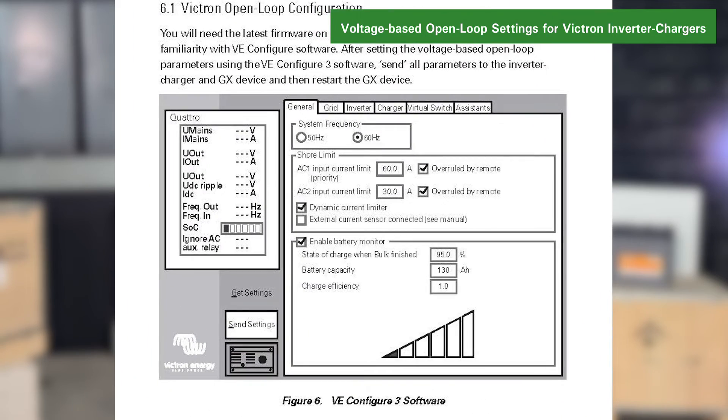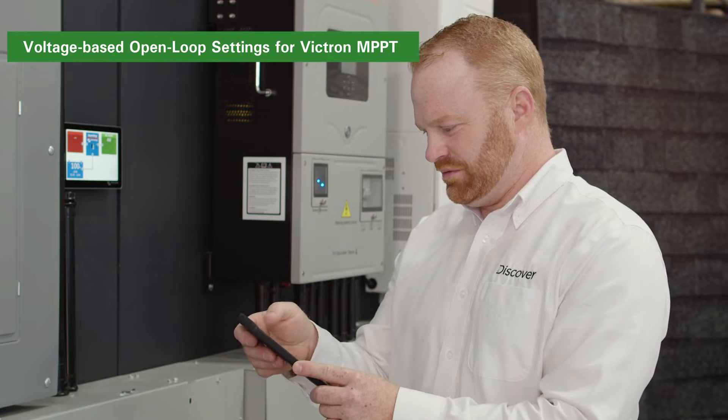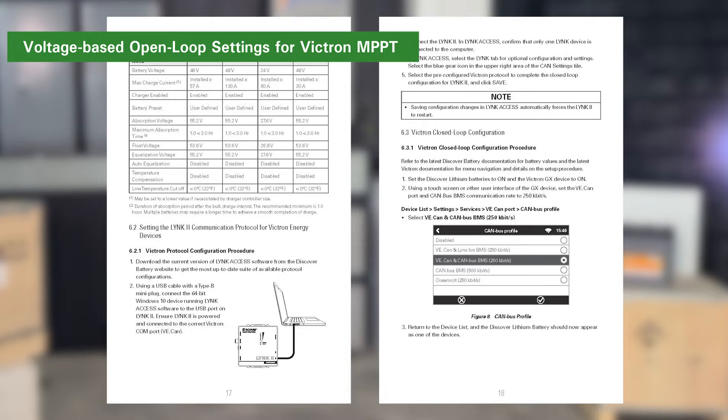After setting the open loop parameters, save all the parameters to the inverter charger and the GX device by clicking the Send Settings button. Restart the GX device after completion. The Victron Connect Bluetooth app is used to configure the voltage-based open loop parameters for Victron MPPT products equipped with Bluetooth. A list of Victron MPPT battery settings can be found in section 6 of the LYNK II Victron user manual.